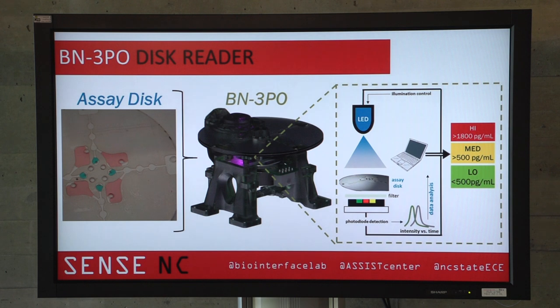There's a close-up of our assay disk with something that doesn't look anything like serum or blood — those are just food coloring so you can see what it looks like. The buffer solution is the pink chamber, and the serum or blood sample would go in the blue chamber. We can accurately control the flow based on centrifugal force. As we spin up, the serum flows, hits the first chamber, picks up our detection analyte, and waits. When we spin a little faster, the buffered solution flows through and forces it through the rest of our detection, the waste comes out the back, and our capture antibodies trap the NT-ProBNP in the detection well, which is then detected via an LED and a photodiode.